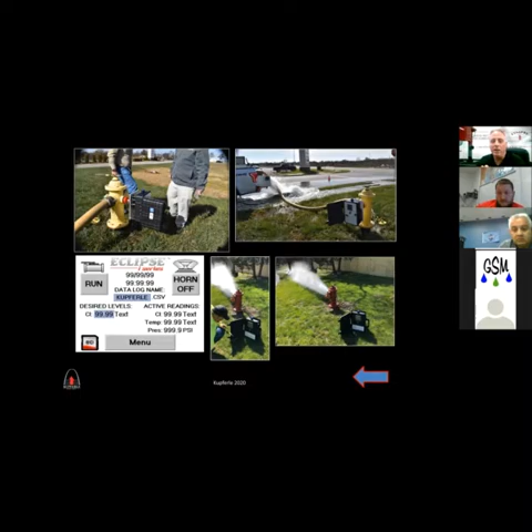So the spec looks like this. This is how it looks when it's either attached to the hydrant or attached with the cord. This is called the Flushing Buddy. It makes your hydrant flushing more effective and more efficient. The device is powered by a 24-volt lithium-ion battery that you recharge, okay? It has a touchscreen PLC, and it flushes the exact amount of water to reach the programmed desired levels that you want to hit with your flushing.